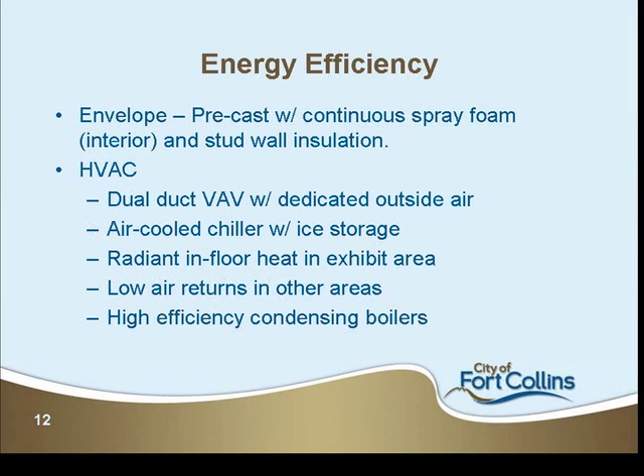Providing the cooling is an air-cooled chiller with ice storage. So at night, when electricity is inexpensive and peaks are low, make ice, and then during the day, that ice can be melted to provide cooling for the building and completely keep that chiller off of the utility peak.